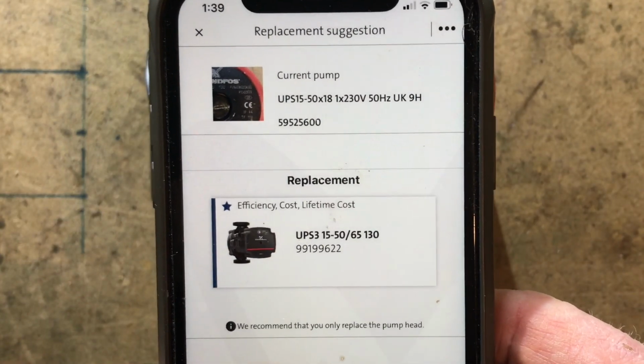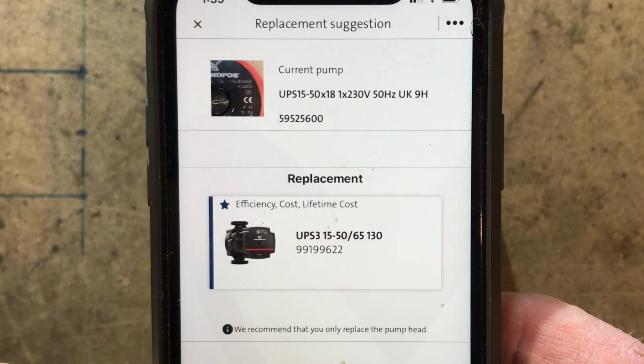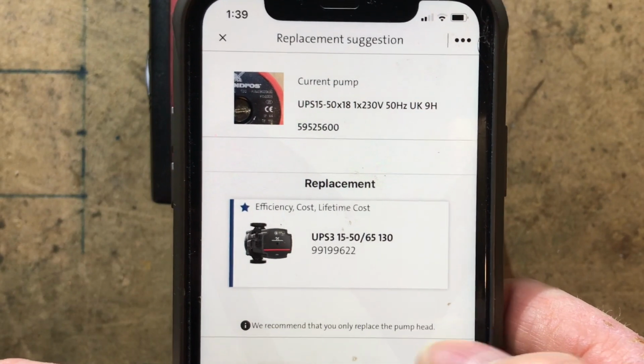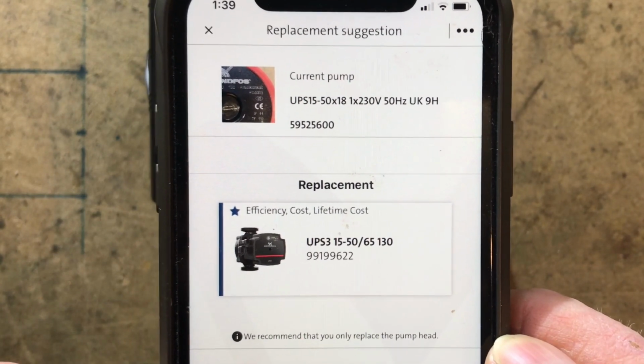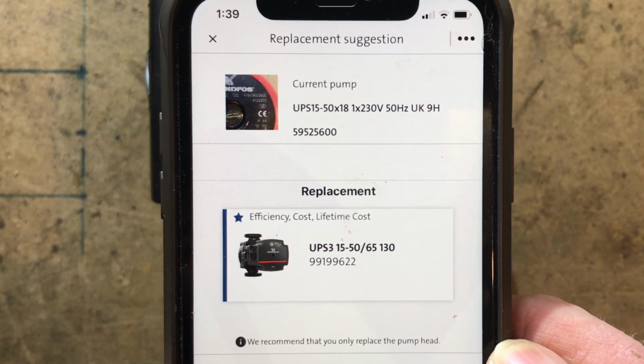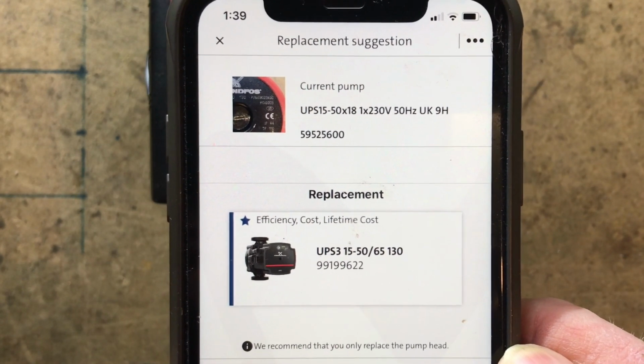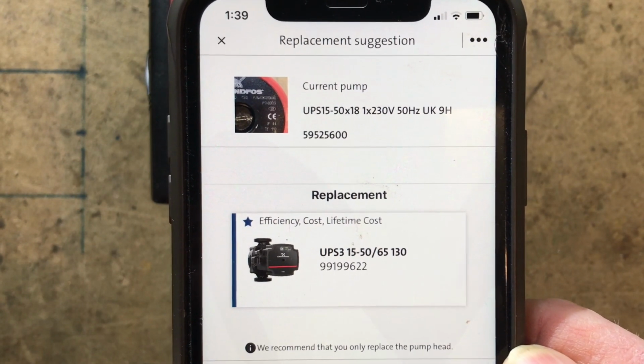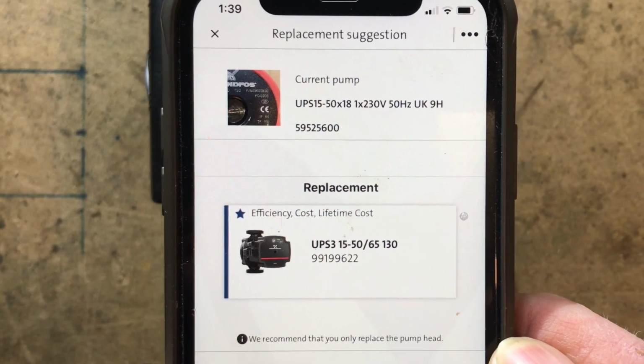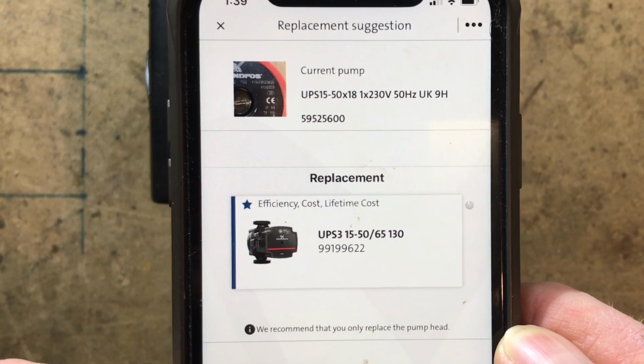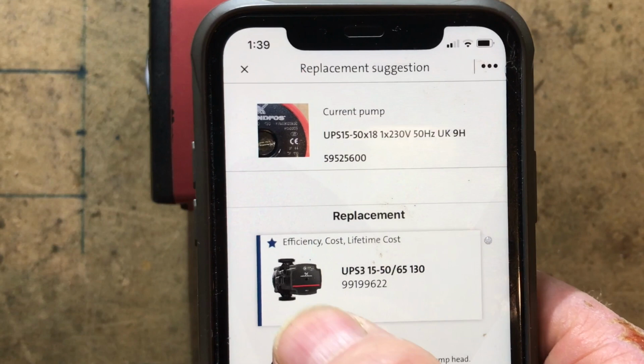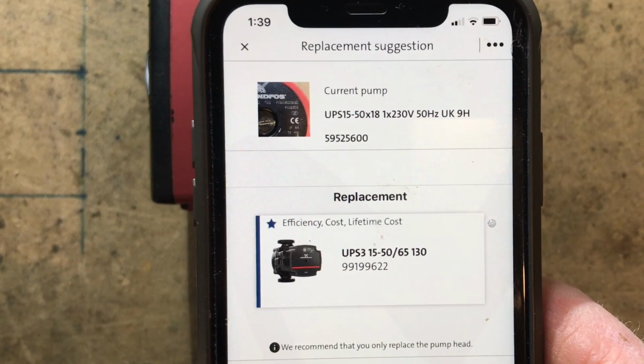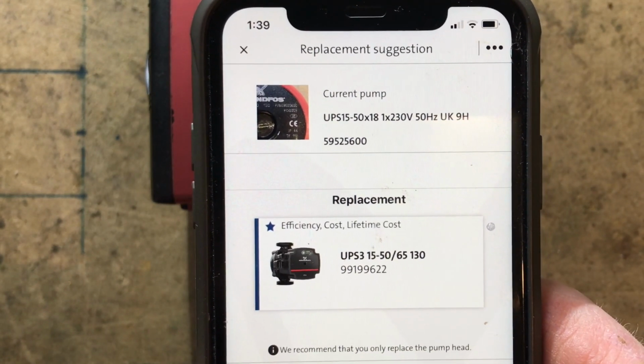And look at that. It's just told me what pump I can use to replace if that was in the boiler. And it says we recommend that you only replace the pump head. So that new pump will still fit on the old body of the old pumps, and they reckon you can go back 15 years on boilers with this. So I think every engineer should be having this app, and this puts in the new UPS 3 pump. So let's go and have a look at this UPS 3 pump then.